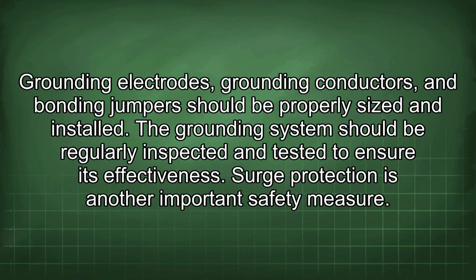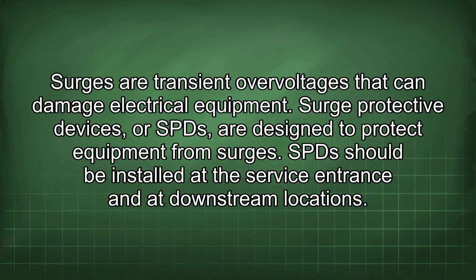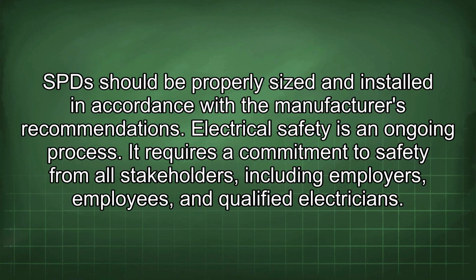Grounding electrodes, grounding conductors, and bonding jumpers should be properly sized and installed. The grounding system should be regularly inspected and tested to ensure its effectiveness. Surge protection is another important safety measure. Surges are transient overvoltages that can damage electrical equipment. Surge protective devices, or SPDs, are designed to protect equipment from surges. SPDs should be installed at the service entrance and at downstream locations. SPDs should be properly sized and installed in accordance with the manufacturer's recommendations.